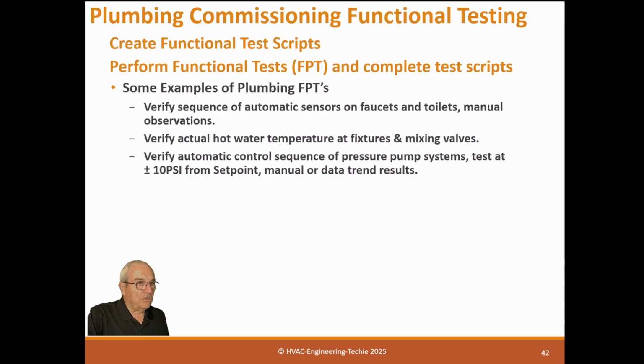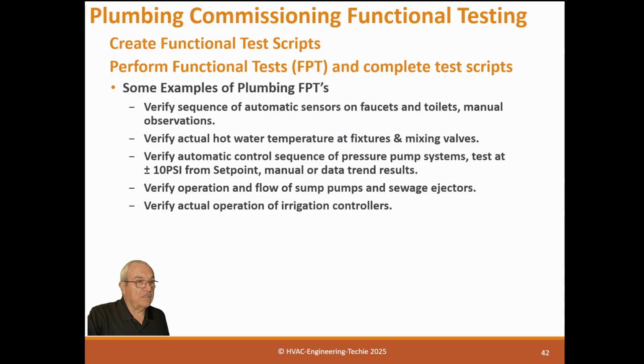Verify automatic control sequence of pressure pump systems. You want to vary the pressure, put it up 10 psi, down 10 psi, and trend the data to make sure the pressure system is doing its job correctly. Verify operation and flow of sump pumps and sewage ejectors. That's pretty easy. You just put enough water down there to make sure it comes on and alarms at the different stages, so you can test those controls on the sump pump. It's a manual functional test, but it's still a functional test.